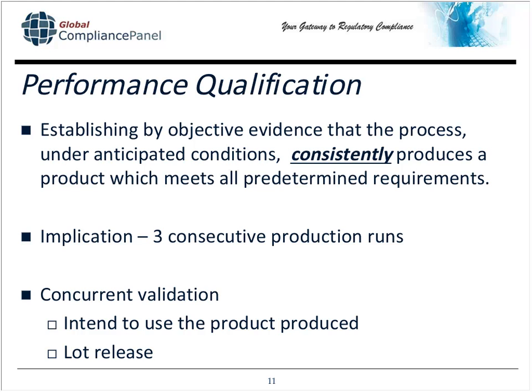What we're going to talk about here is concurrent validation, during which the product that's produced and validated, that's used in the PQ, is going to be used. So for these 3 consecutive production runs, I'm going to make my normal production size of, let's say, 1,000 pieces. And based on the ANSI standard, I'm going to sample 80 pieces from each lot. Well, I've got 920 other pieces from each lot that I could conceivably use. The way I'm going to use these products is by lot release. Once the first lot finishes its validation, I'm going to test the 80 pieces. They will pass, hypothetically, and I can release those 920 pieces into stock if I have to.